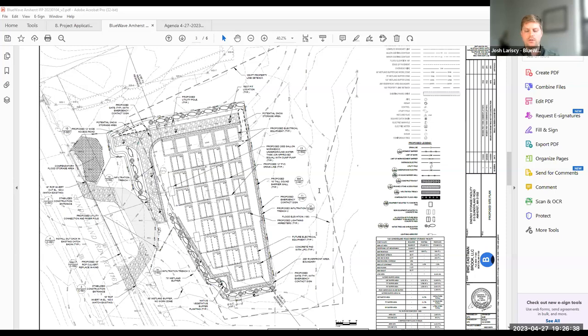It would be flush with the ground, 16 feet high, typically a 4 to 6 inch width barrier. The materials can vary, but we're anticipating specking it as sandwich construction, metal panels sandwiching sound dampening material. That would go around the entire perimeter of the site, with gates also designed into the sound wall to ensure there's no gap in sound transmission.